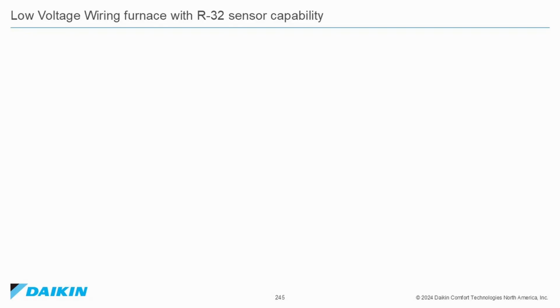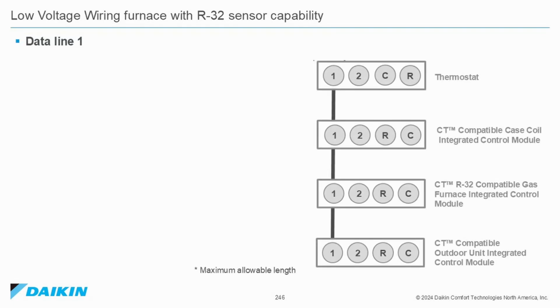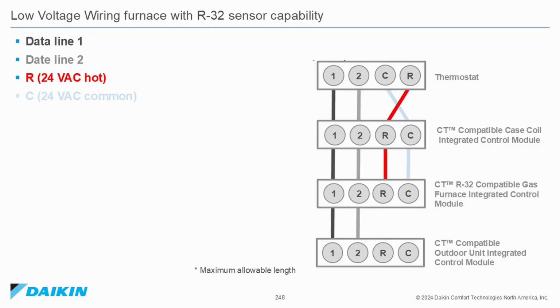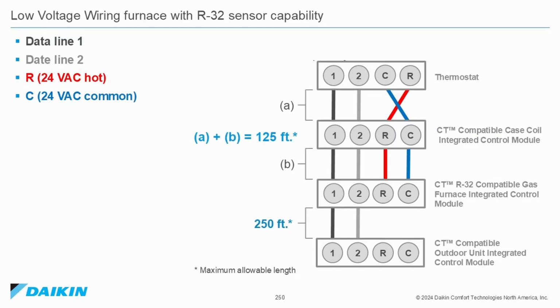Low voltage wiring to a furnace with R32 sensor capabilities. Data line 1 is shown as a black wire. Data line 2 is the gray wire. R, the 24 volts hot, is the red wire. C, 24 volts common, is the blue wire. Notice that between the thermostat through the coil to the furnace is a maximum of 125 feet. The communication line is all that's needed between the furnace and the outdoor unit, and that would be a maximum of 250 feet.